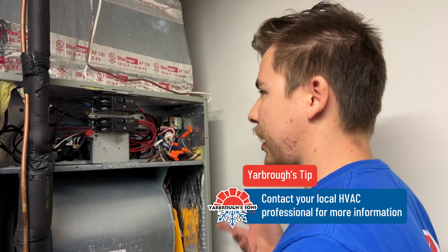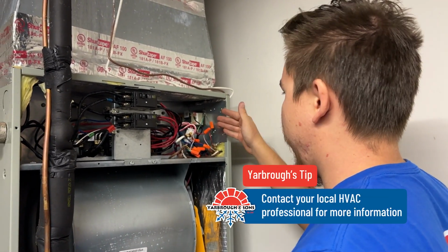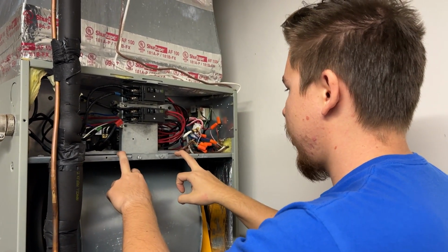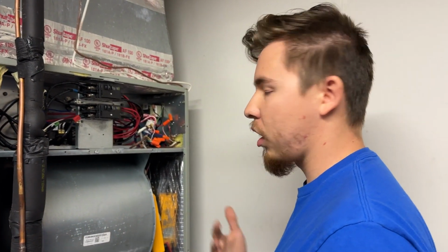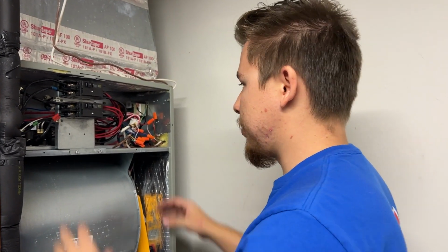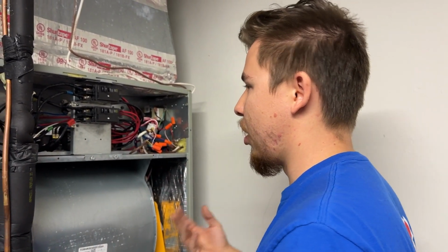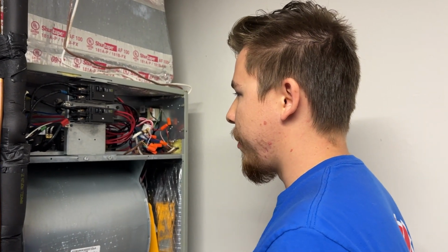So you've got fusible links that can go bad. You've got your transformers over here. You've got your two contactors. But for your gas one, you've got more components that can fail. This is just more of everything joined together that can kill the whole circuit with one part going bad. But with the gas one, depending on which part, it can still run.